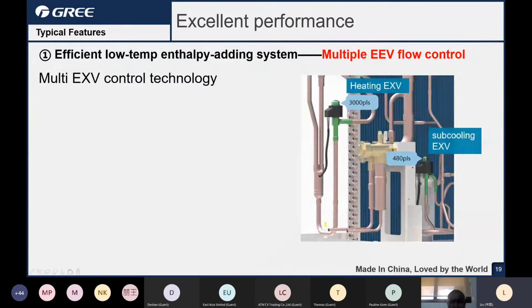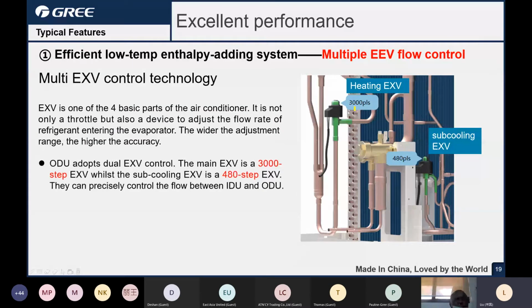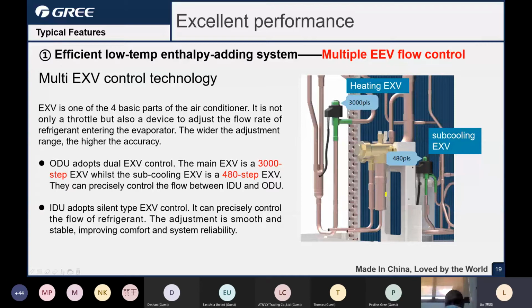And for the outdoor units, now we have a look at this picture. Okay, this is a subcooling expansion valve. We already see it, 480 pulse steps. But for the heating expansion valve, that's a big change for the GMV6. In the previous generation, the heating expansion valve is just 480 pulse steps. But now we changed to a bigger expansion valve to increase the diameter of the valve, so that when the unit runs in heating, the circulation of the refrigerant will be better. That's the 3000 pulse step expansion valve. Okay. For the indoor units, the expansion valve is also 480 pulse steps.